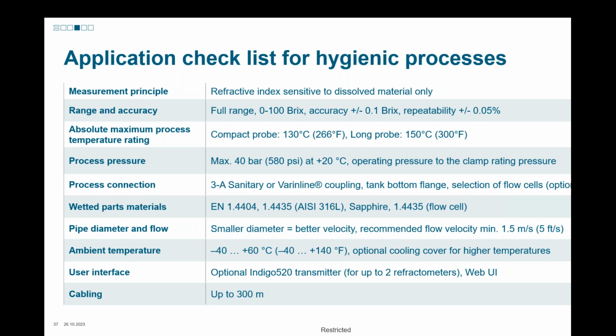If somehow there's a mismatch between the lab and our reading, you have to choose a dog in the race. Which one are you going to trust? If for whatever reason you trust the lab more than our reading, we can change that. We can actually make it read what you need simply by doing an offset or even a field calibration. The Brix scale is very well defined. If ours is reading 22 Brix, 22.1 Brix, it's probably right, but it may not agree with the lab. And we can give it an offset and make it read what you'd like. So now you get a more consistent agreement with the lab.